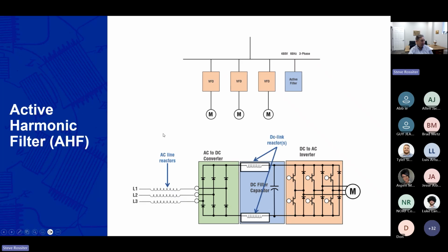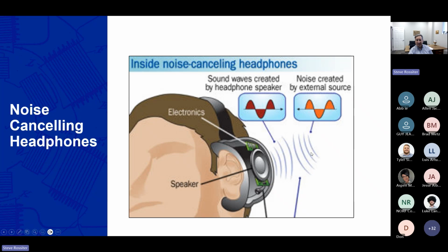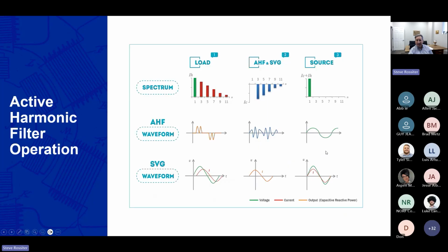And the last technology I think I'm going to show here is one that we've really seen a lot of recently, the active harmonic filters, where you take a device that is in parallel with the rest of the bus, could have multiple drives, and I'm going to just speed along here a little bit faster. It's almost the same technology as noise canceling headphones, where you just generate a waveform that is the opposite waveform to cancel this out. Might be this, it ends up with this. So the same thing you hear audibly with noise canceling headphones. You can do the same thing with active harmonic filters, and there are some very significant advantages of these devices.